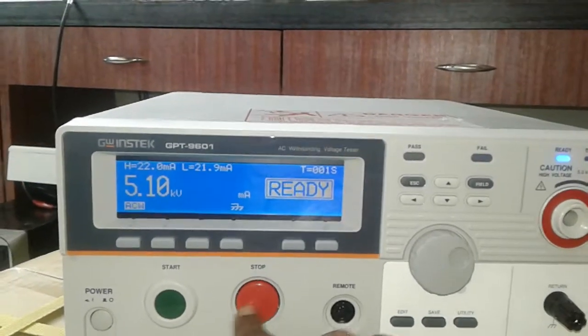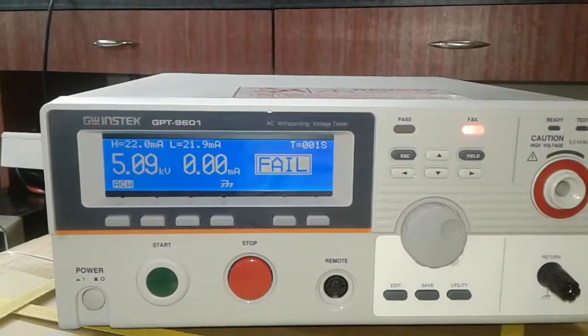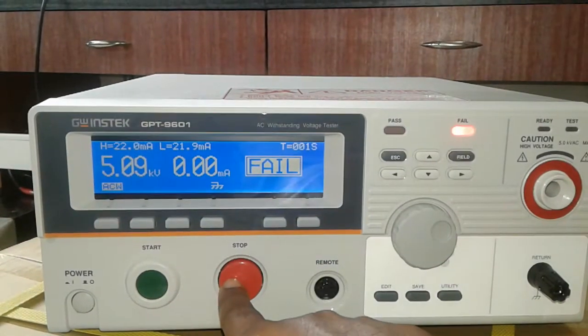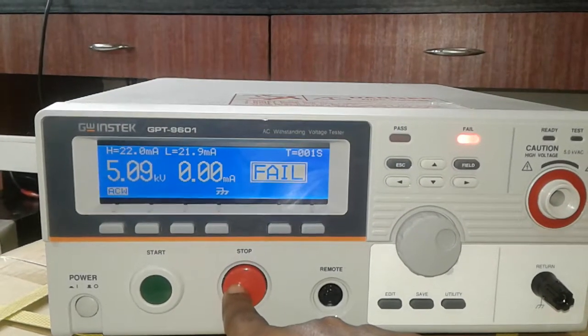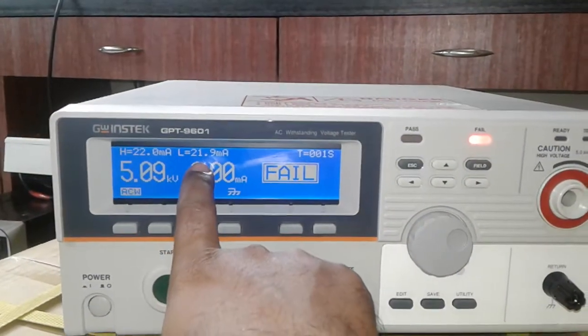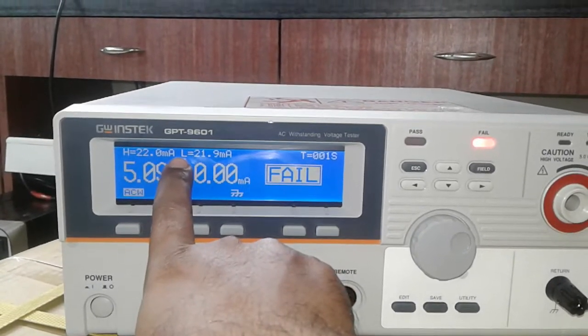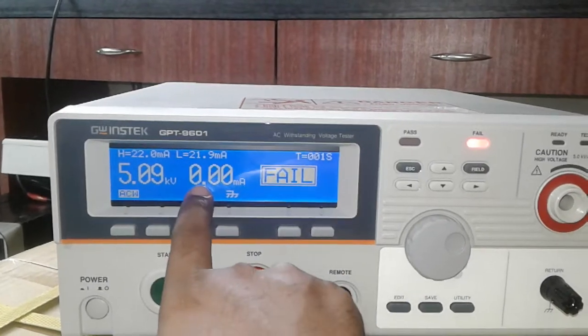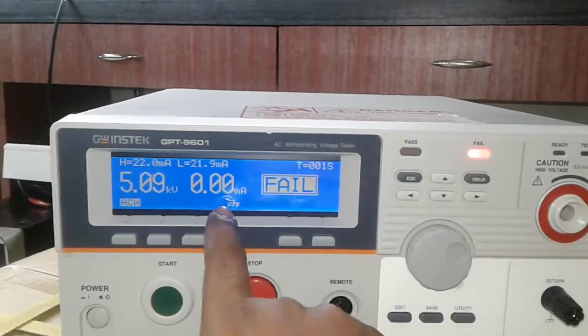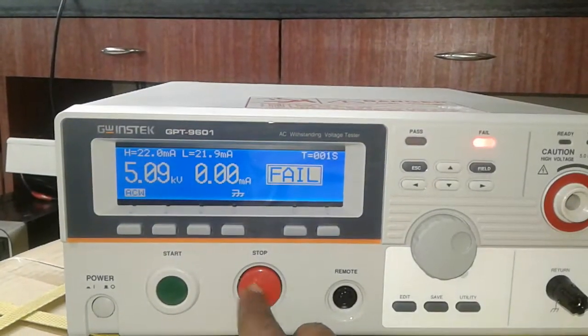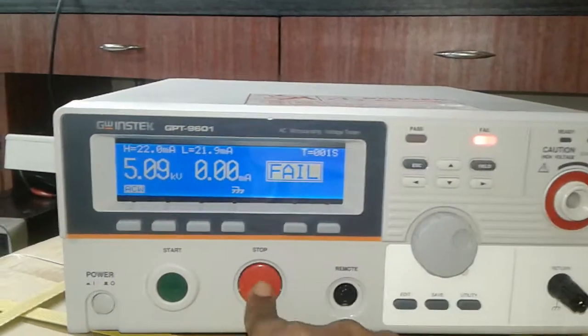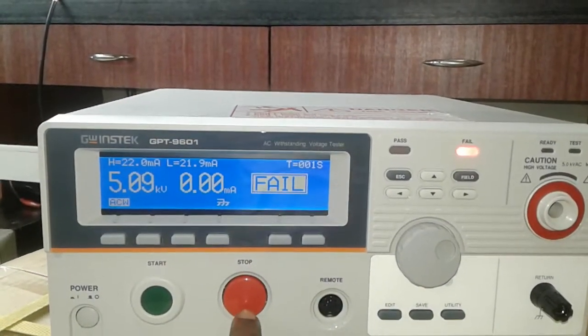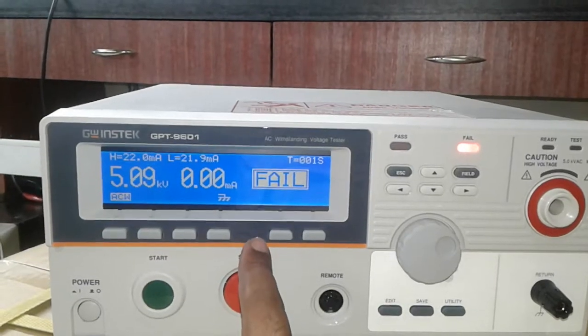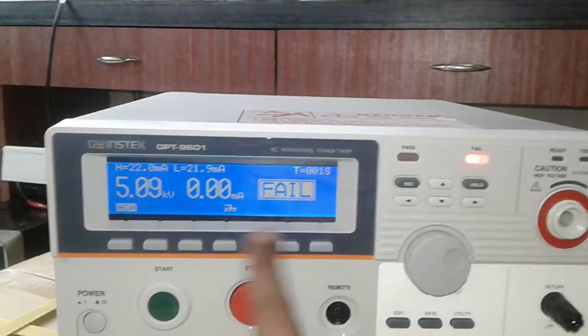Okay, save. Okay, now we have set the low limit to 21.9 milliampere, and the high limit is 22 milliampere. The bandwidth is very small and we are getting the result 0.00 milliampere, so that's why the result is fail. Just press once, and the buzzer will be off.